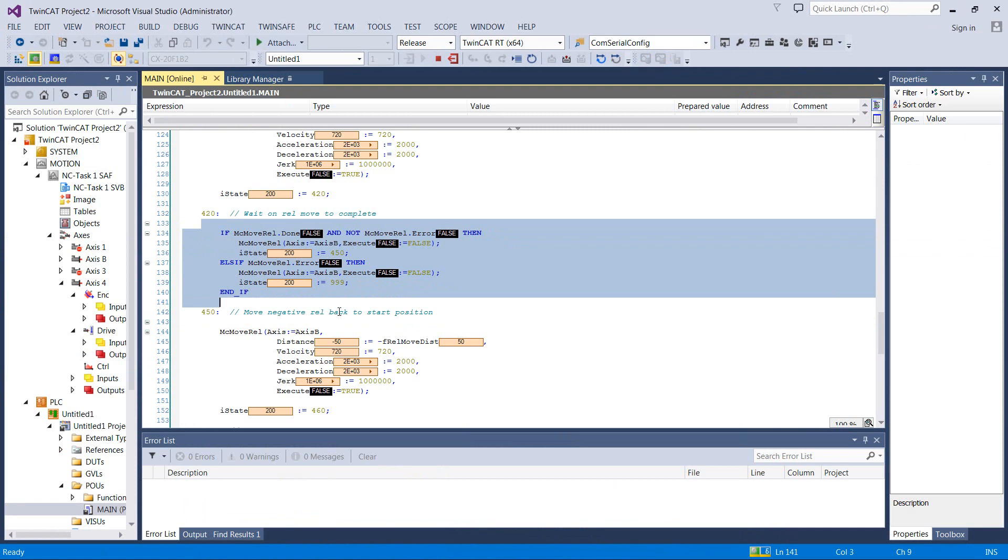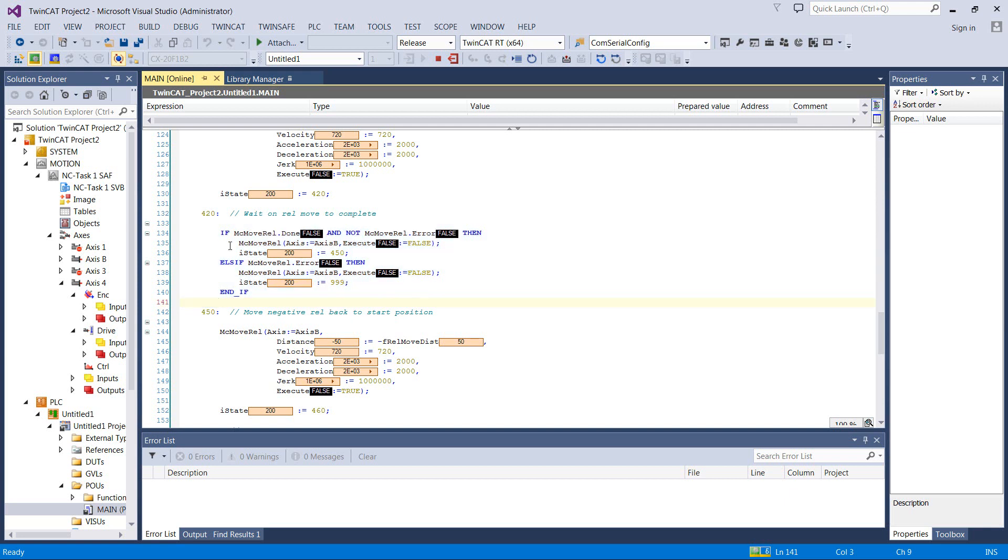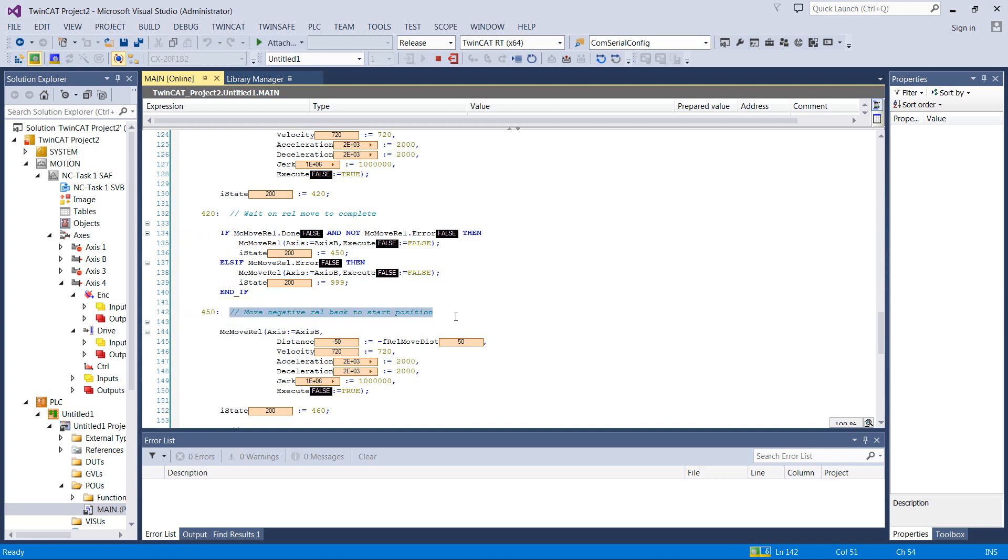So looking at this code is a great way to handle that, as well as just moving back to the main program there, you can put timers in all of these states and record them. So you have state transition times, histories, stuff like that. So I've found that using a combination of a state history array, which I believe we talked about in the first PLC series, but using a combination of a state history array and timers for moves and things like that, instrumenting your code, and then also being able to go and scope it. Those two things together make debugging and postmortem analysis really nice. So that's basically it that I wanted to show you on that.